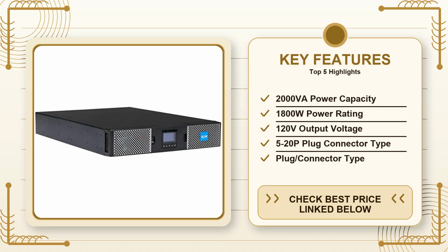Let's talk about the kind of environment where a double conversion UPS really shows its worth. You're probably familiar with the two basic UPS architectures: standby, or offline, and online. Standby units simply switch to battery when they detect a dip, which means you get a brief interruption, often enough to cause a crash or corrupt a file on a PC that's writing data. An online unit like the 9PX runs your load through the inverter at all times, providing clean, uninterrupted power even during the tiniest variations in the grid. If your workload includes high-end workstations, network switches, or even a small server that can't afford any hiccup, the extra layer of protection can be a lifesaver.